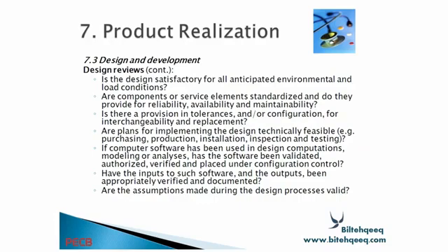Are plans for implementing the design technically feasible? For example, purchasing, production, installation, inspections, and testing. If computer software has been used in design, computation, modeling, or analysis, has the software been validated, authorized, verified, and placed under configuration control? Have the inputs to such software and the output been appropriately verified and documented? Are the assumptions made during the design process valid?